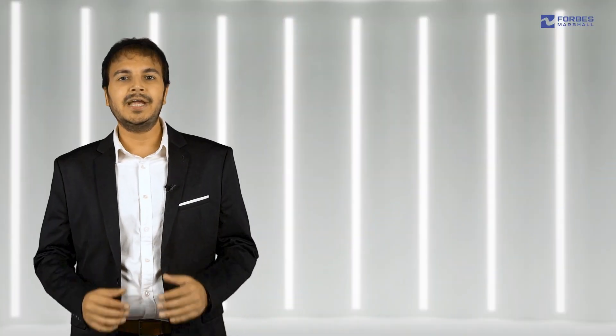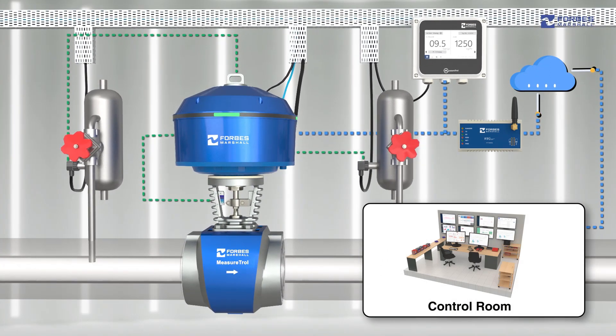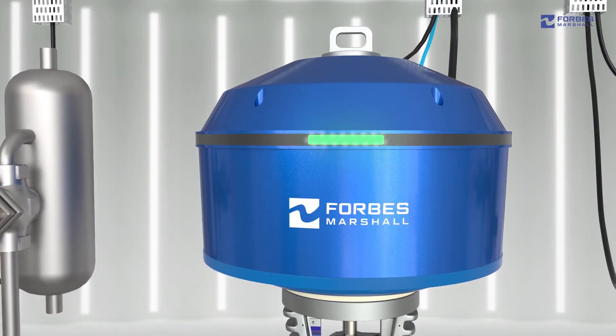Auto-tuning of the PID action can be configured via Bluetooth using the mobile phone app or through Modbus. Indicative steam flow is transmitted to the cloud through a remote terminal unit. Built-in LEDs display the health of the MeasureTrol, enabling proactive action to prevent unplanned shutdowns.